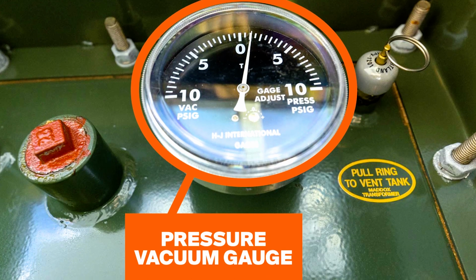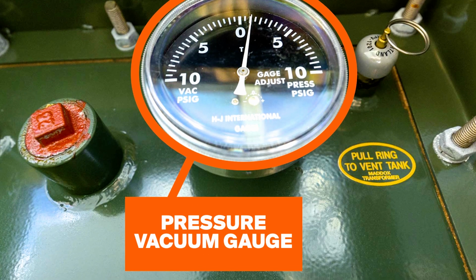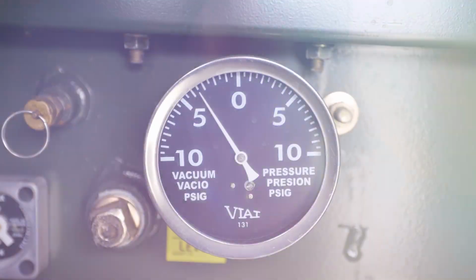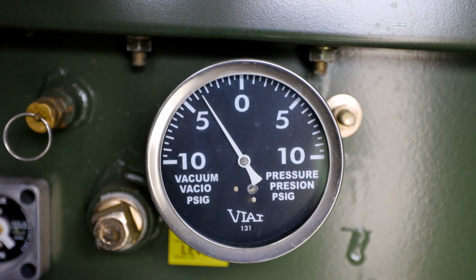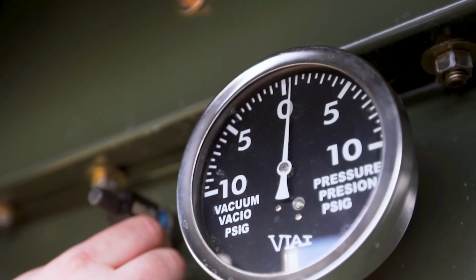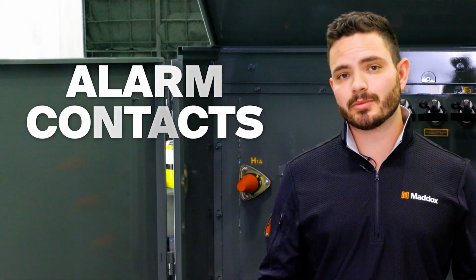Next, the pressure vacuum gauge indicates the internal transformer tank pressure. As the transformer oil warms and cools inside the tank, the gauge dial will fluctuate in positive and negative directions. Next, let's look at alarm contacts.